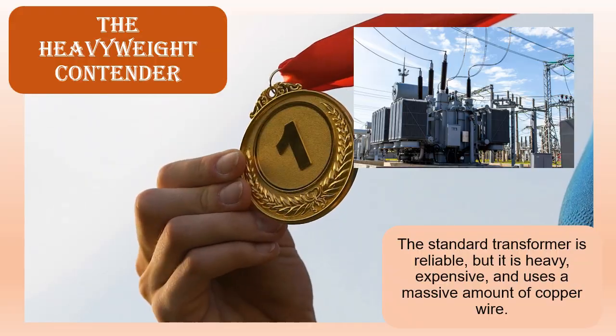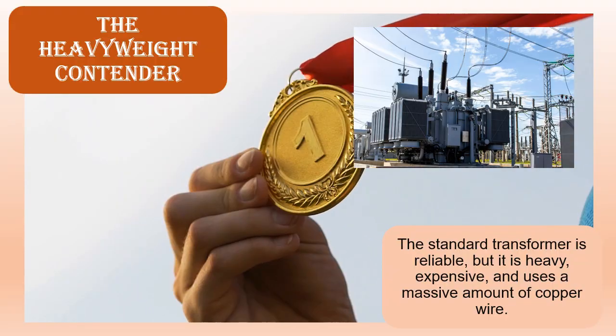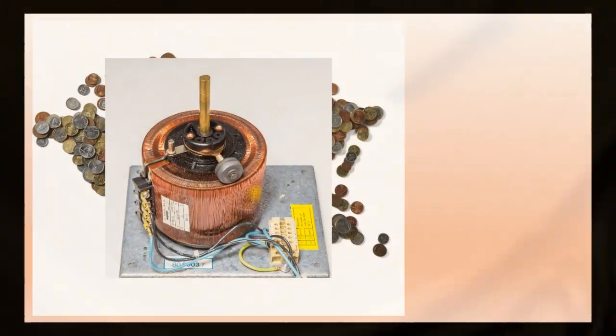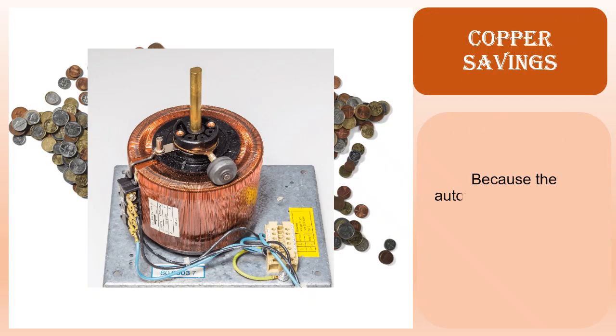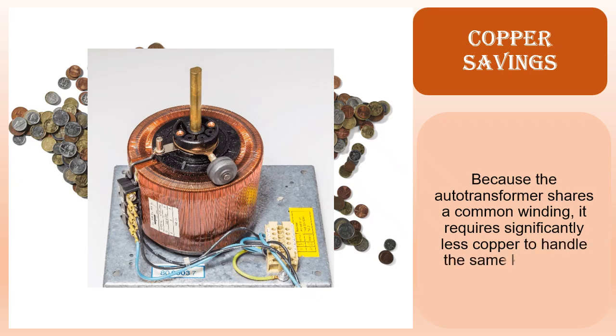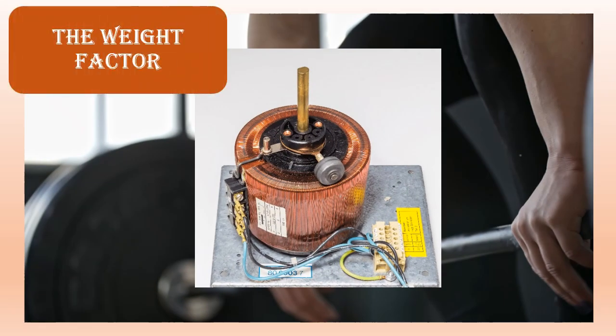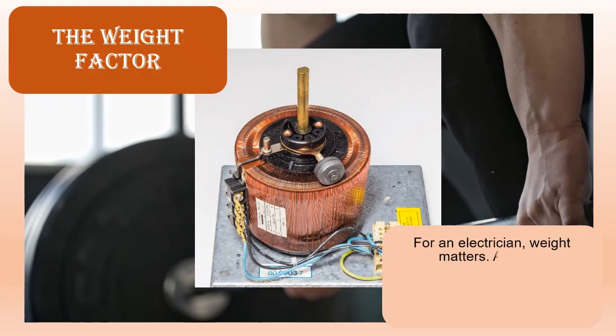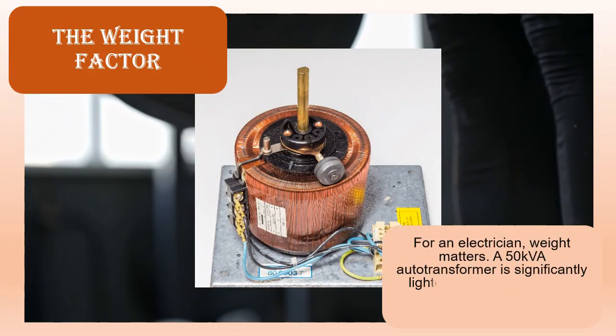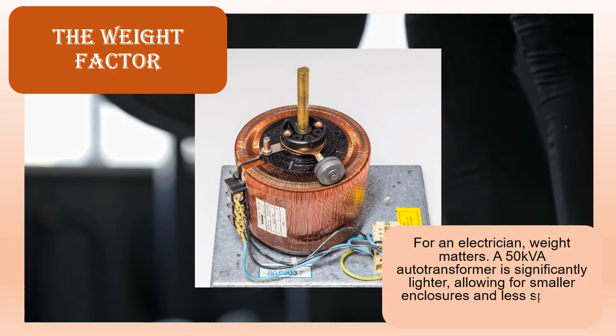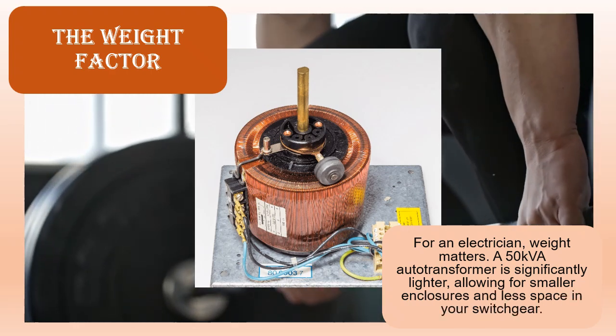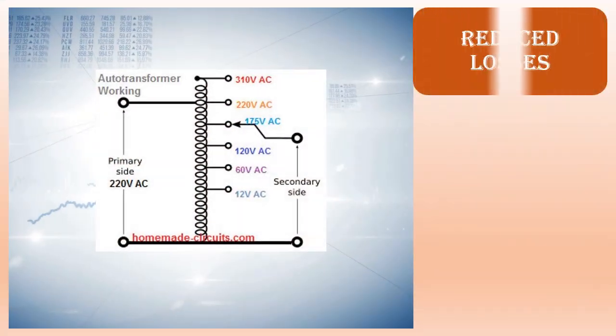A 50 kVA autotransformer is significantly lighter, allowing for smaller enclosures and less space in your switchgear. Reduced losses. With less wire length, ohmic I²R losses are minimized. The excitation current needed to magnetize the core is also reduced. Better regulation. The lower internal impedance of an autotransformer means the voltage drop under load is significantly less. This results in superior voltage regulation.